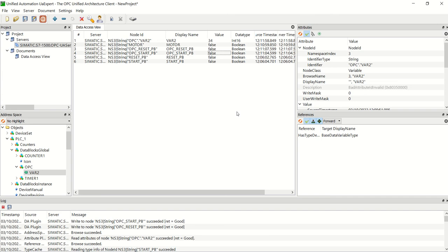Really what we're just doing is connecting the OPC client software, which is this, to the OPC server, which is in the PLC, and we're just looking at some of the values of the tags to identify their namespace IDs. Because when we open up Node-RED, we're going to do the exact same thing. We're going to connect it as an OPC UA client, connect it to the PLC, read these values in, but as I said, it's just not as easy as dragging and dropping as what we were doing there. I need to actually type these string identifiers in. So it should make a little bit more sense in the next video, but that's how we can set up an OPC UA protocol with TIA portal and the software here, the UA Expert.